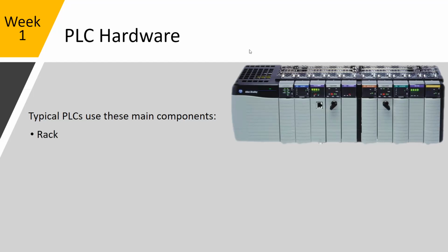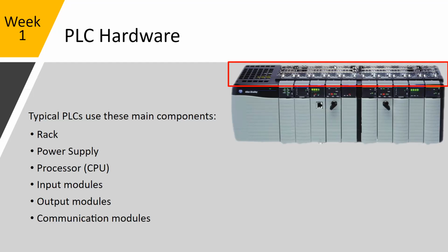So what we have here is a rack. So anytime you hear me or anyone use the word rack in association with PLCs, that's going to be this kind of box that the cards mount into. I think, yeah, so that is the PLC rack. That is similar for a lot of different platforms. So the GE Fanuc, Schneider has a rack. Not all of Allen Bradley's, but a lot of Allen Bradley's, they'll have a rack. Even some Siemens processors, they've got a rack that mounts the cards to it. In the back of the rack is what's called a back plane. So the back plane will transmit data from the cards to the processor. This here is the power supply.